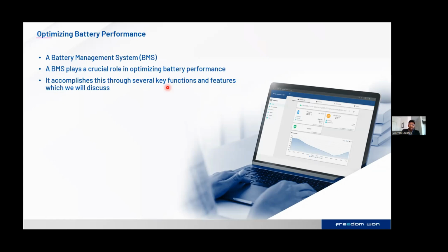Busbar sizing is the interlinks between the cells to minimize IR losses. We have proper conductor cables used, and in some instances HV batteries, high voltage batteries. Higher volts means lower current, so less IR losses, which makes it more efficient. This is primarily linked to the selection and design of the battery process. We can use all of these things in designing the battery, and this improves it in terms of minimizing losses.